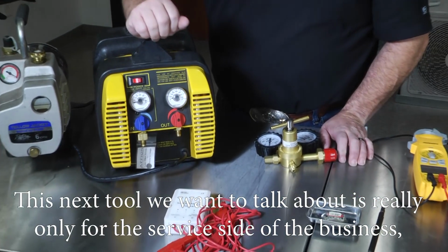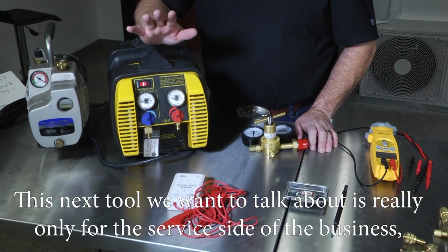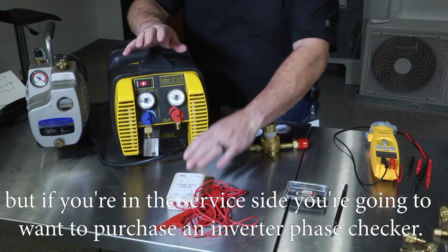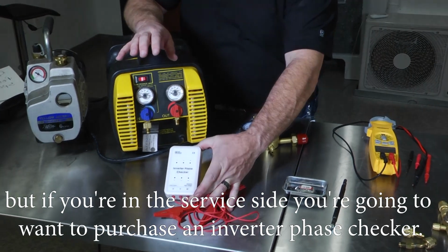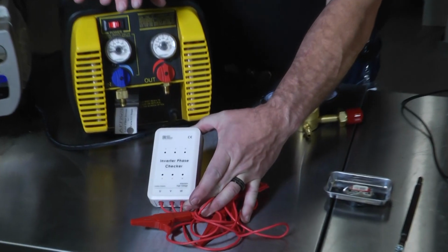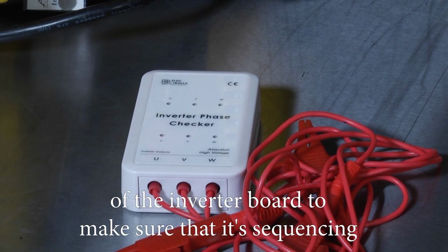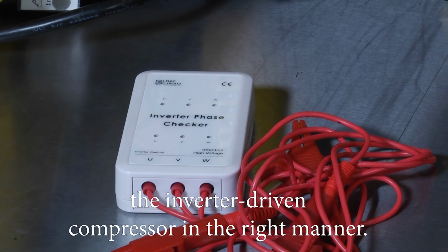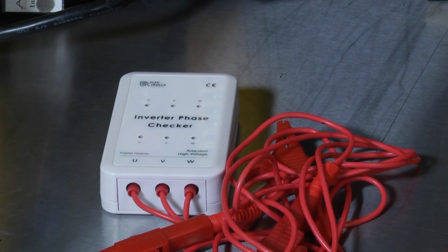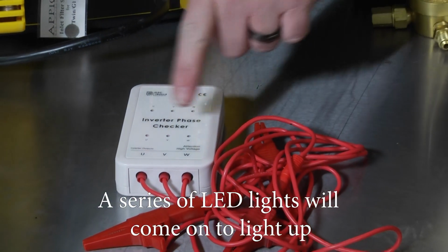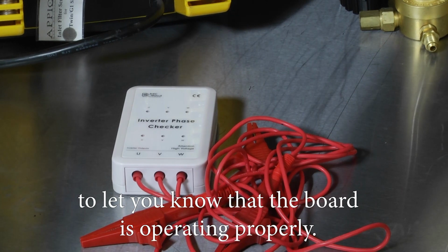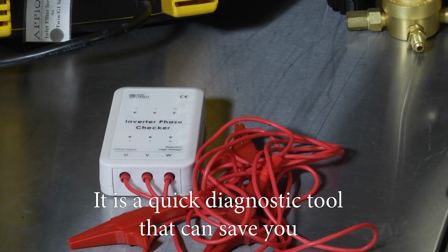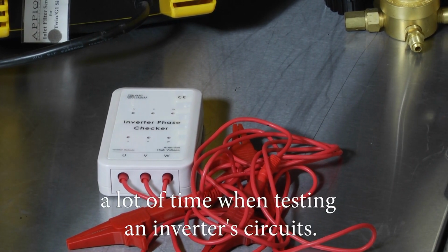This next tool that we want to talk about is really only for the service side of the business, but if you're in the service side, you're going to want to purchase an inverter phase checker. This is designed to hook up to the machine to check the output of the inverter board to make sure that it's sequencing the inverter-driven compressor in the right manner. A series of LED lights will come on to let you know that the board is operating properly, and it's a quick diagnostic tool that can save you a lot of time when testing an inverter circuit.